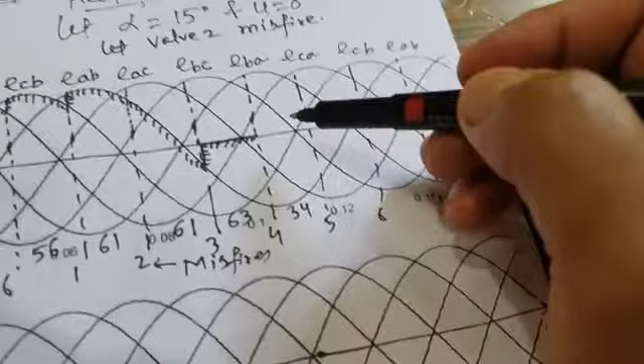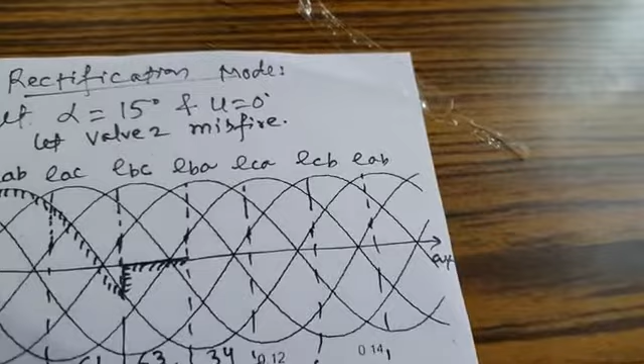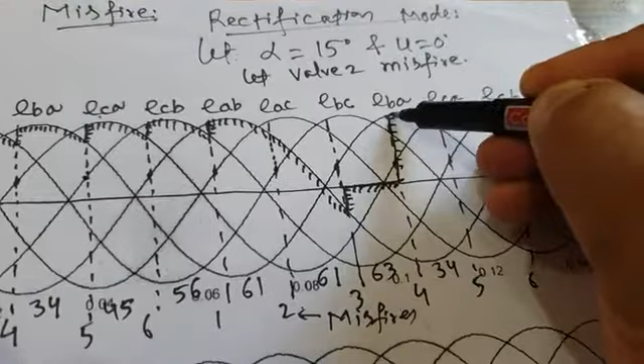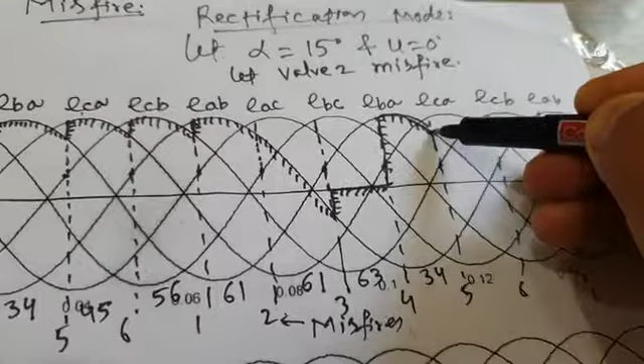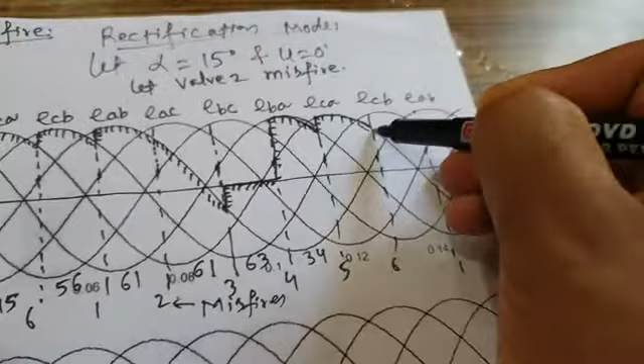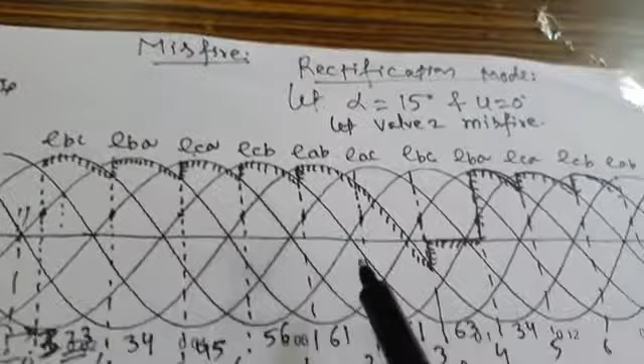When the 3-4 pair is conducting, what is the load voltage? 3 is conducting, so your positive bus voltage is EB. 4 is conducting means negative bus voltage is EA. Your load voltage is EBA. Where is EBA? You have to find EBA. This is EBA. Let me verify it. Yes, it is EBA. So your load voltage changes from 0 to EBA. It will remain EBA till the next instant of firing, which is when 5 is fired. As soon as 5 is fired, normal operation of the converter resumes, and it will continue like this. So this is the nature of your load voltage waveform.